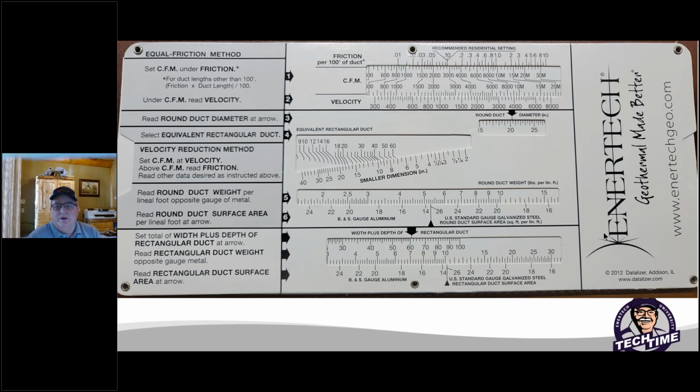This is one that Enertech used to have, had from many years ago, that you can actually use. They actually recommend ductwork design of a 0.10 static pressure, but in my career, and I think a lot of people look at, we like to do designing ductwork on a static pressure of say 0.12 in the supply, and then we'll go to a 0.08 in the return.